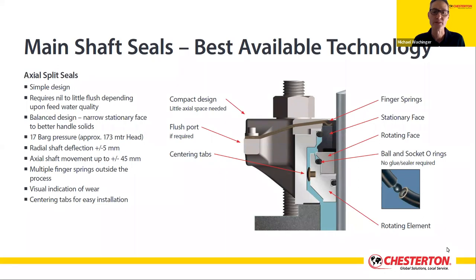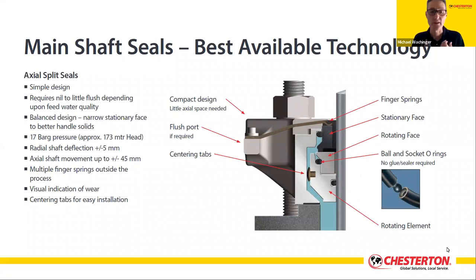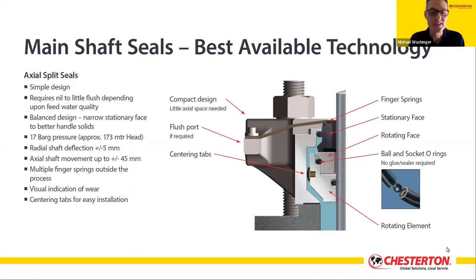However, with seal face balance learned from various mechanical seal applications over the years, larger size designs have now been applied to many hydroturbine main shafts with good success. To date, many hundreds of these types of seals, ranging from 150mm shaft size up to 860mm, have been running between 10 to 20 years of service — with an estimated average in Chesterton Hydroturbine Seal's case of roughly 15.4 years service life without breakdown or repair, with minimal need for flushing systems. Also, these designs are able to be split into two and sometimes four pieces for ease of handling and installation.